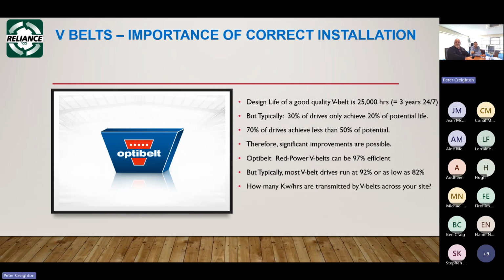So if you look at how many kilowatt hours are transmitted by V-belts across your site, looking at all your air handling units with your supply and your return, typically, everywhere I go in larger manufacturing, they would have a couple of 100 kilowatts, because they would have 37.5 and 45 kilowatt supplies and 22 kilowatt and 18.5 kilowatt returns. You start adding all of them together and you say, oh my God. Just by setting up a V-belt correctly, you will achieve at least 5%. I say at least because I'm never promising anyone that they get more than 5, but everybody does in your energy cost.